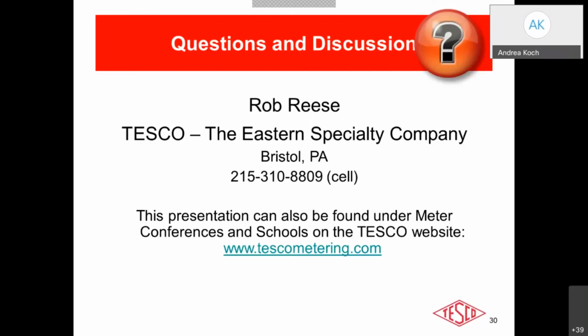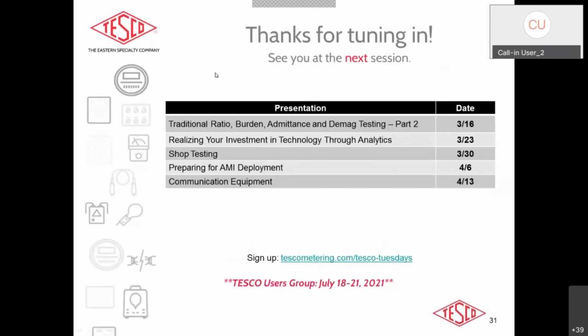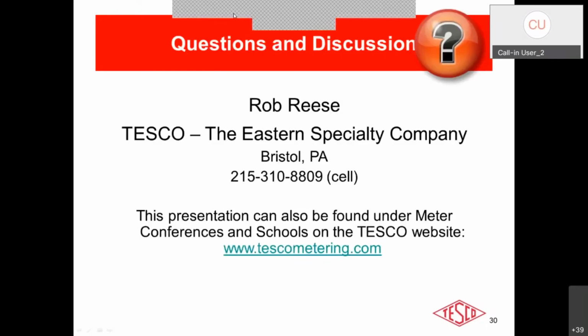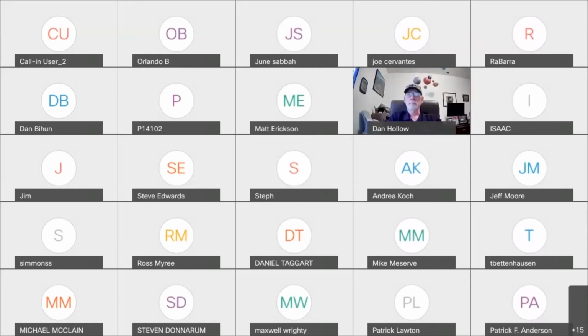So another question that just came in, how do I test high accuracy 0.15 transformers? Oh, okay. Yes, the very same way that you would test like a 0.3% CT. But in those cases, instead of looking for a shift of 0.3% as you apply the additional burden, your make or break point is 0.15%.